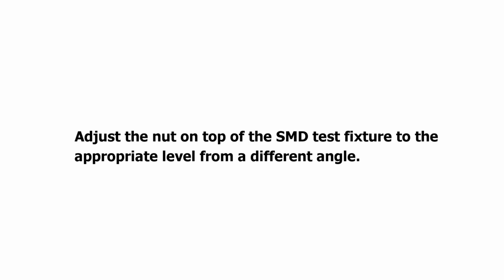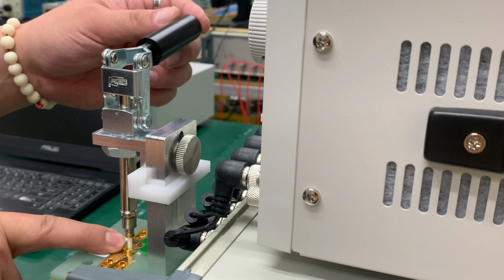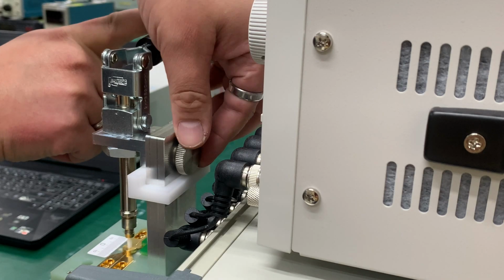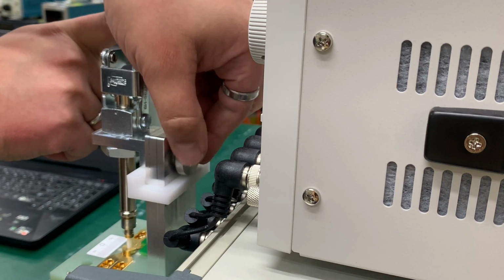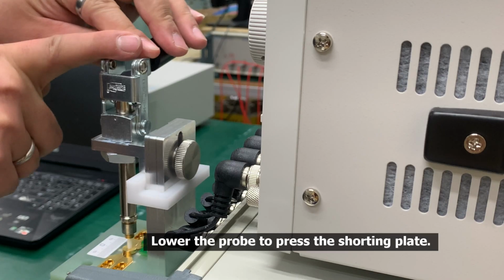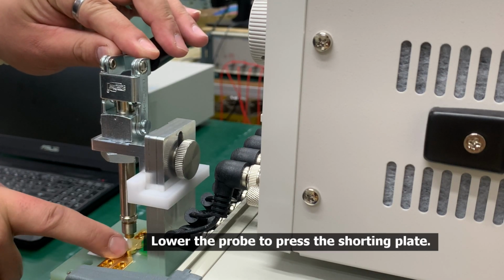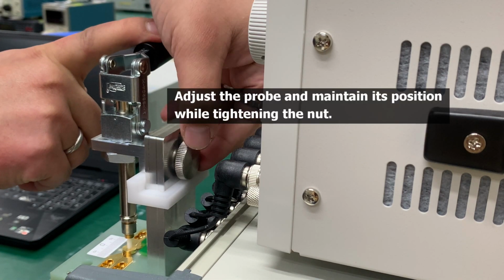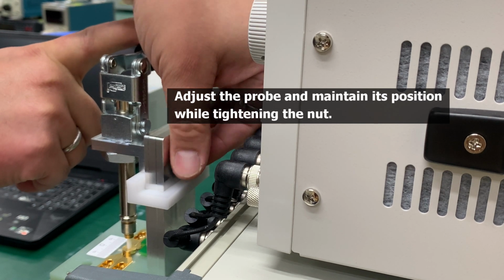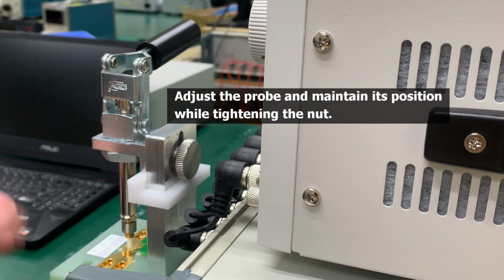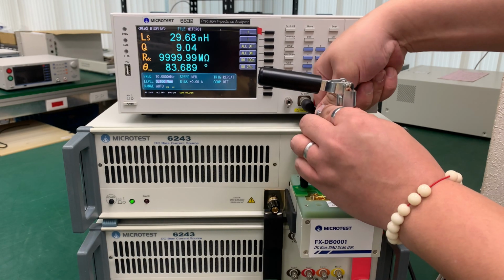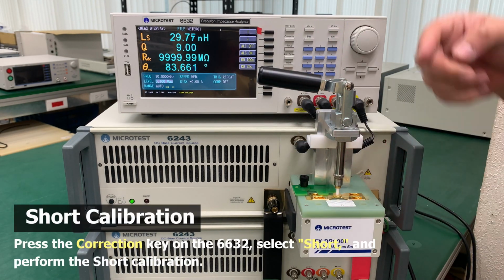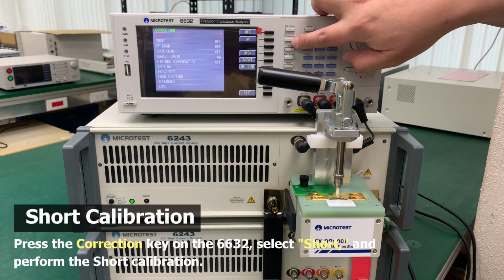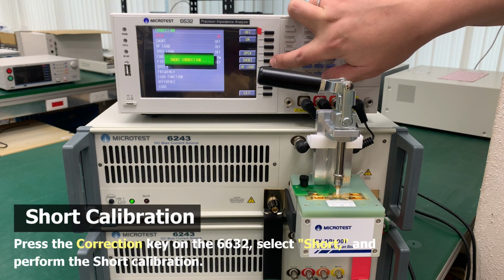Adjust the nut on top of the SMD test fixture to the appropriate level from a different angle. If the probe does not touch the shorting plate, loosen the nut, press the probe down to the shorting plate, and then tighten the nut. Press the correction key on the 6632, select Short, and perform the short calibration.